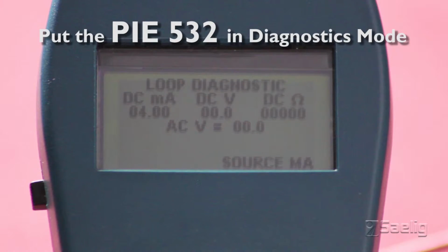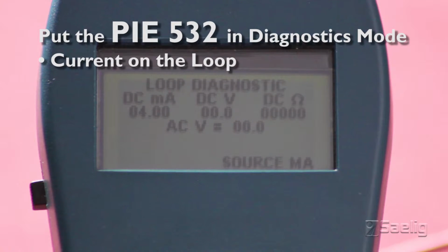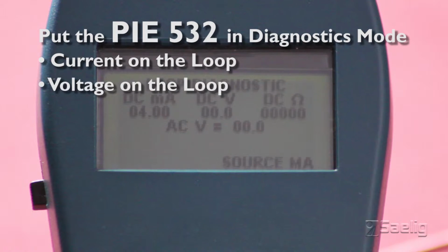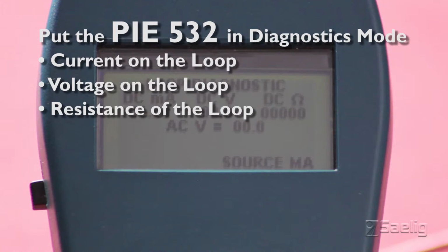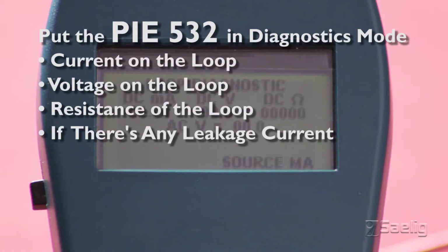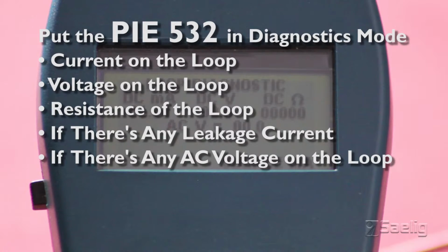The 532 also has one of our patented diagnostic functions. Simply put the calibrator into diagnostics mode. The display will tell you current on the loop, voltage on the loop, resistance of the loop, if there's any leakage current, and also any AC voltage that can be on the loop.